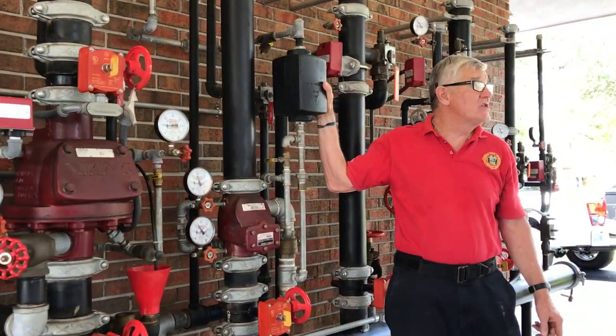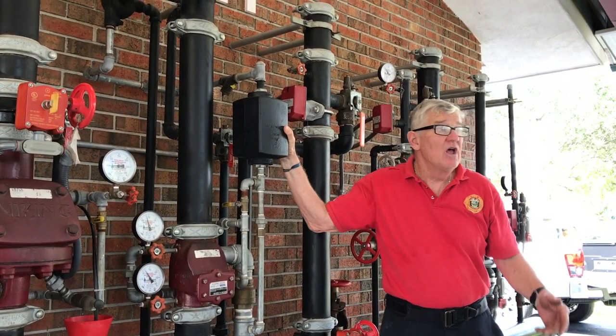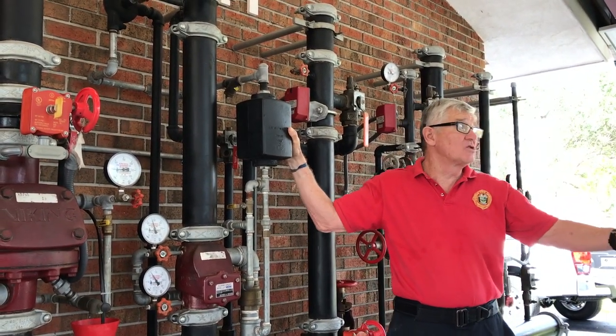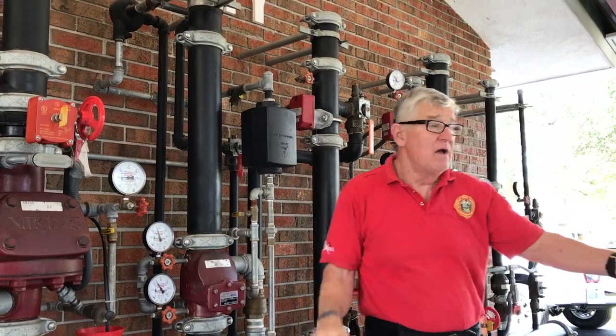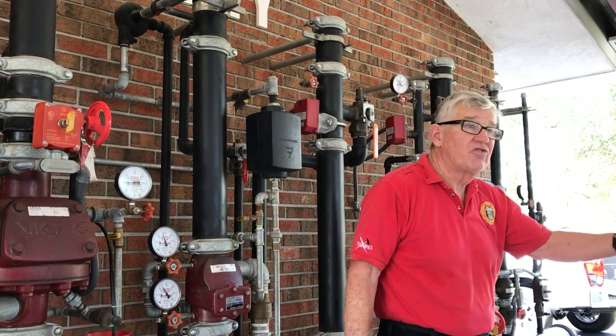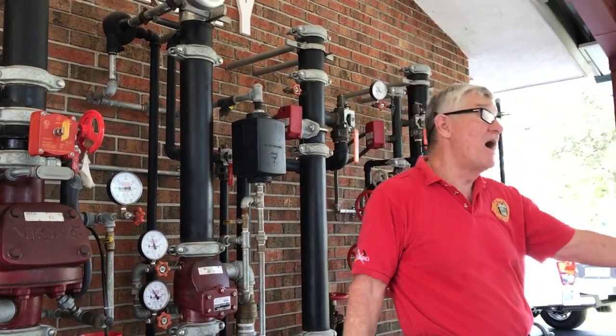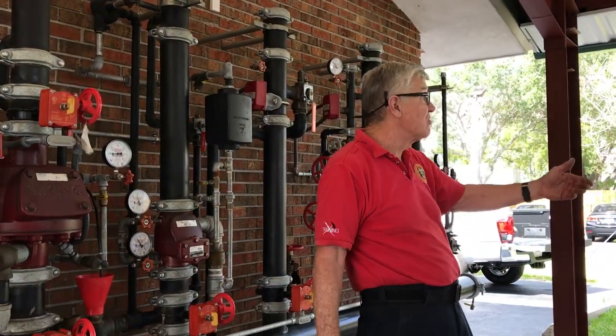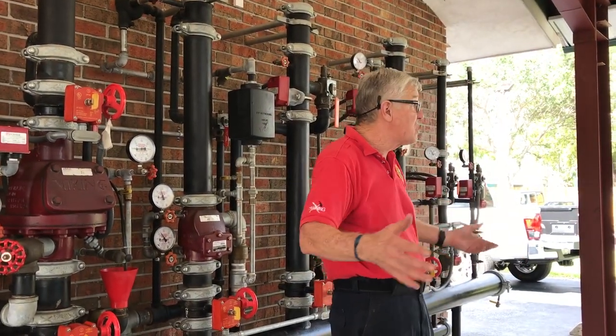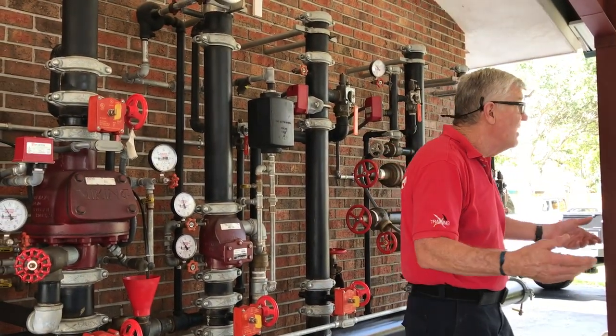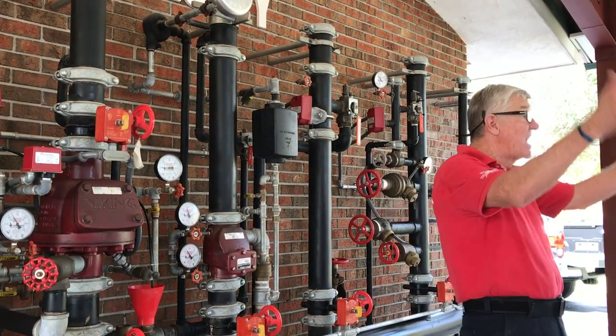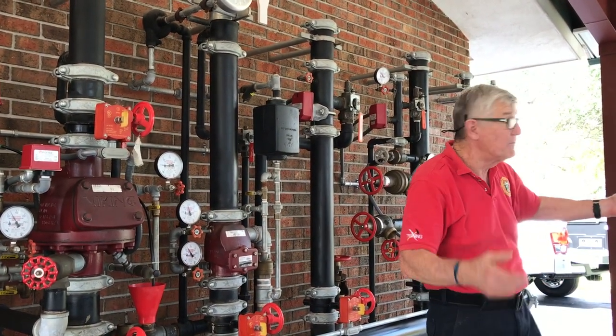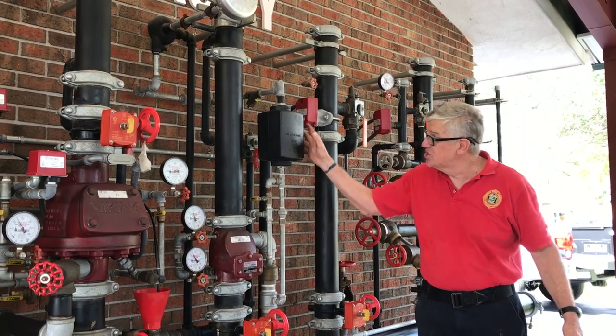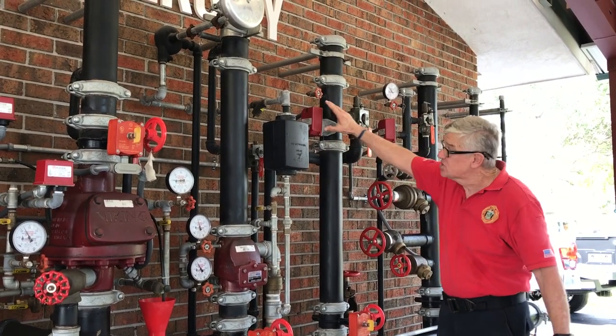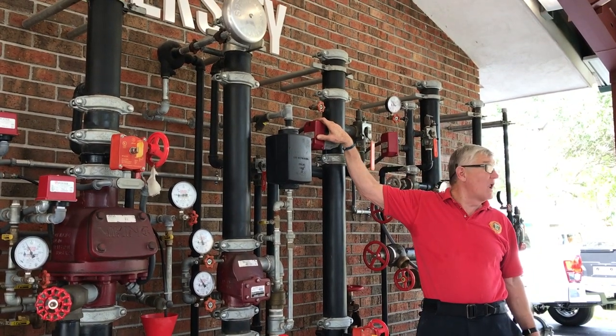we call a retard chamber, because there will be surges in sprinkler systems, as you well know, because 4, 5, 6 o'clock in the morning, when are you responding on water flow alarms? That's during the time when people are taking showers, flushing toilets, the water utility kicks on extra pumps through the surge in the system. To compensate for surges on the newer systems, there's a delay in the water flow alarm.